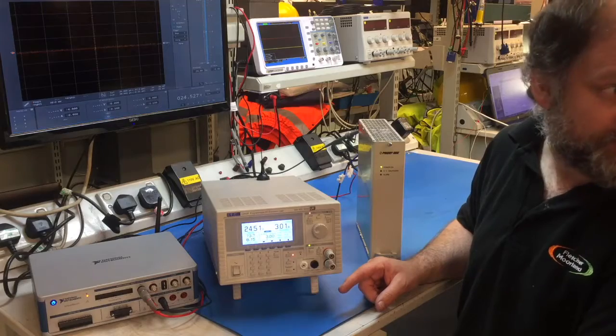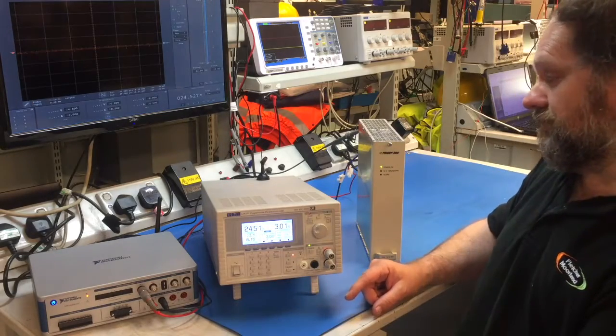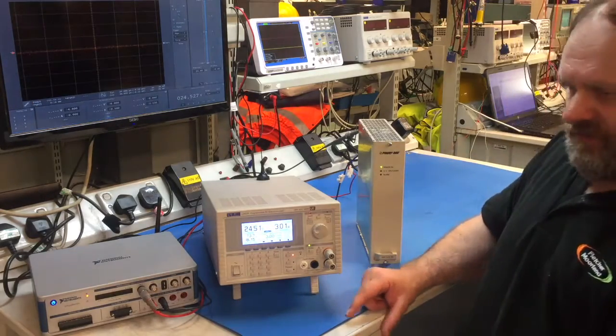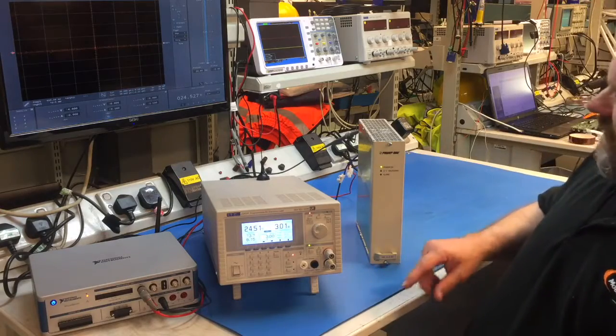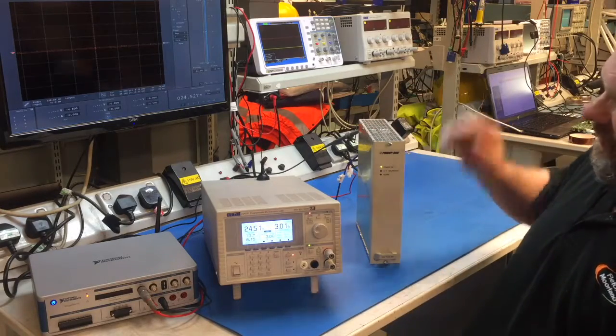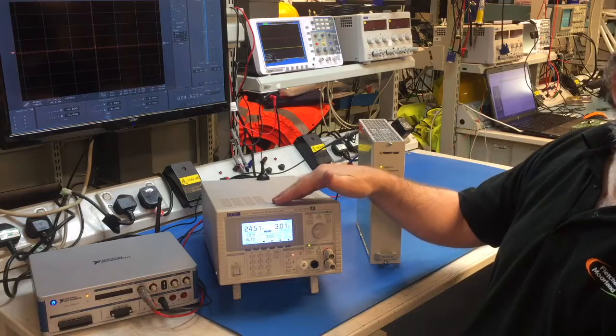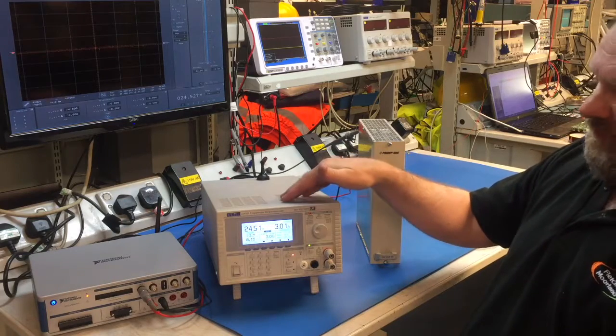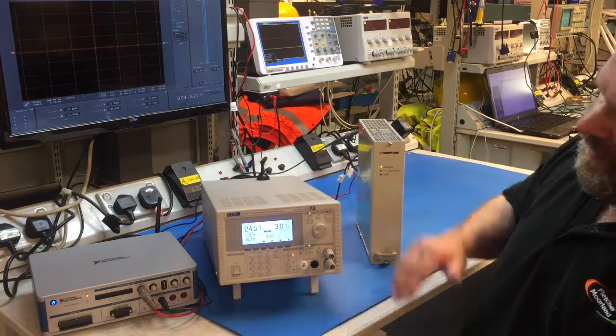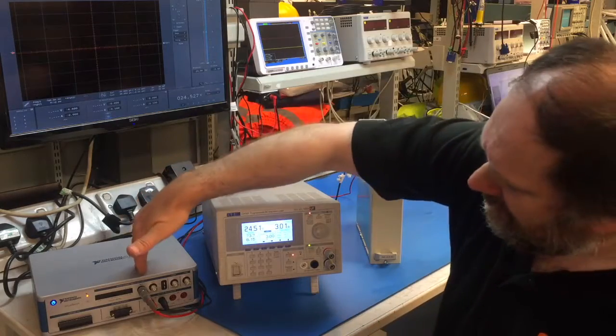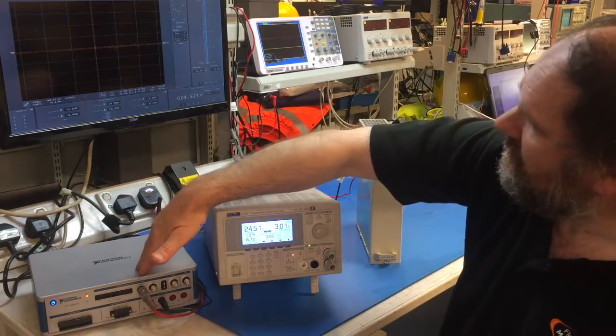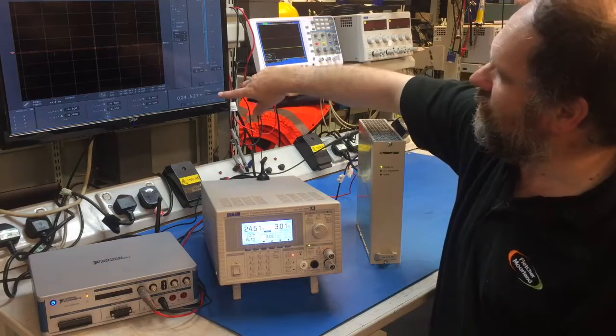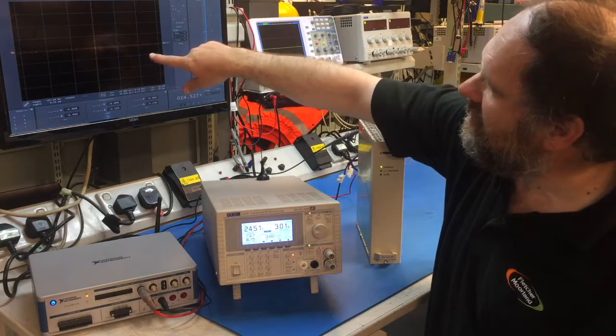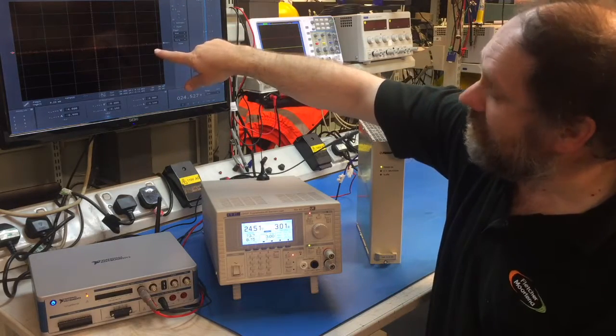Okay, can you just run through the equipment we're using to show what tests are being carried out? Certainly. We have the power supply, and we have an active load, which gives us a variable load on the power supply across its working range. We have an analyzer, a virtual bench analyzer, which gives us the terminal voltage on the power supply and the AC noise on the output.